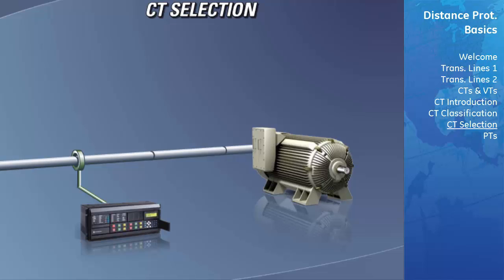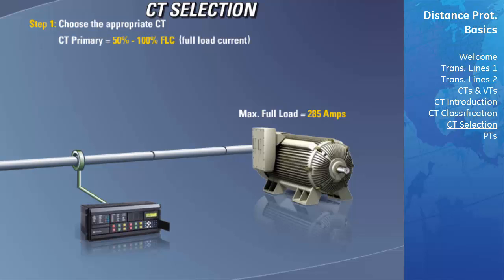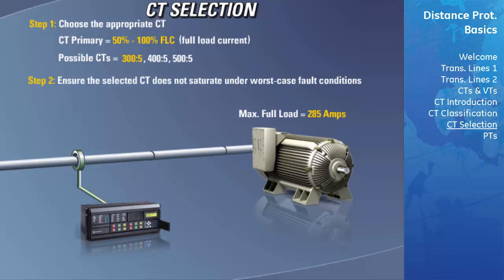Let's assume we have a motor that draws a maximum full load current of 285 amps. The first step is to choose the appropriate CT. It is customary to select a CT with a primary rating falling between 50 to 100% of the maximum full load current of 285 amps. Possible CTs would be 300 to 5, 400 to 5, and 500 to 5. We would select the CT closest to 100% — the reason is that the higher the CT ratio is over the full load current, the less sensitive the CT will be. Since accuracy is always imperative, we select a CT with a 300 to 5 amp conversion, where the primary rating of 300 is closest to the 100% primary rating. If that CT saturates under worst case fault conditions, a higher ratio CT such as the 400 to 5 may need to be chosen.